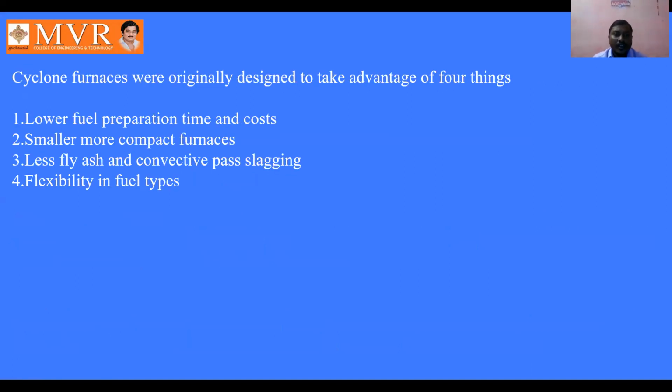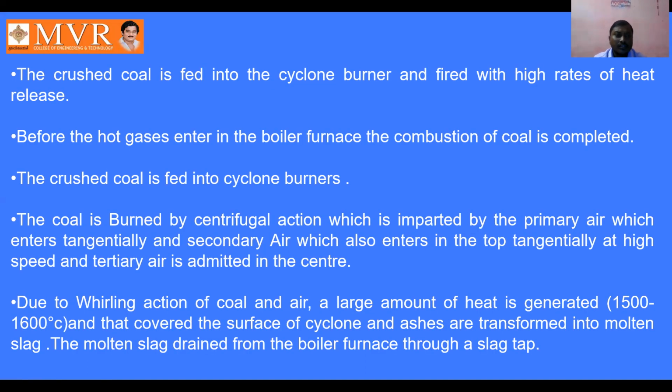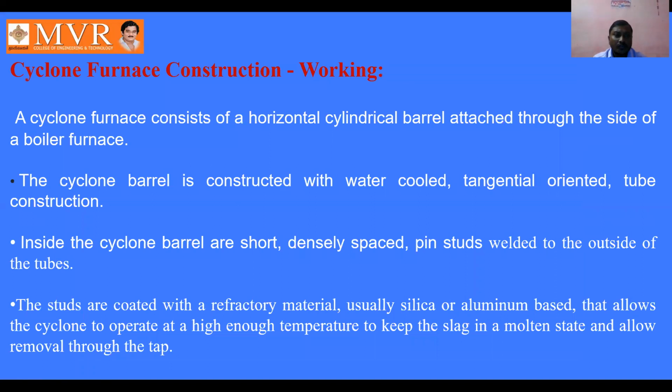We have some advantages here. Lower fuel preparation time and cost are achieved in the cyclone furnaces, and the furnaces are smaller and more compact. There is less fly ash and convective pass slagging, and there is flexibility in fuel types in this cyclone furnace process.